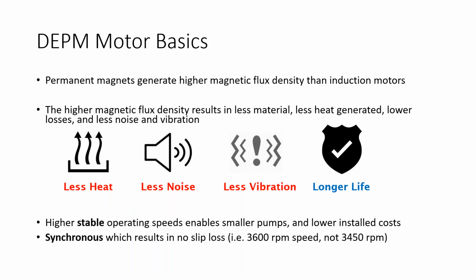Also, permanent magnet motors generate what they call higher magnetic flux density than the induction motors. What that means is that you have less material, less heat, and lower losses with less noise and vibration. Overall, the whole system becomes lighter. There's higher stable operating speeds, which enable smaller pumps and lower installed costs. They're synchronous, and this is where the trick is. They're synchronous, so there's no slip loss.